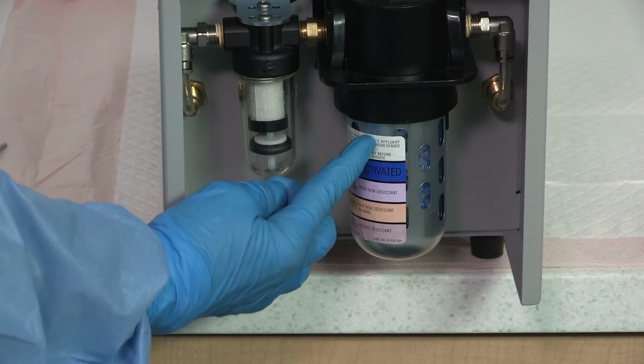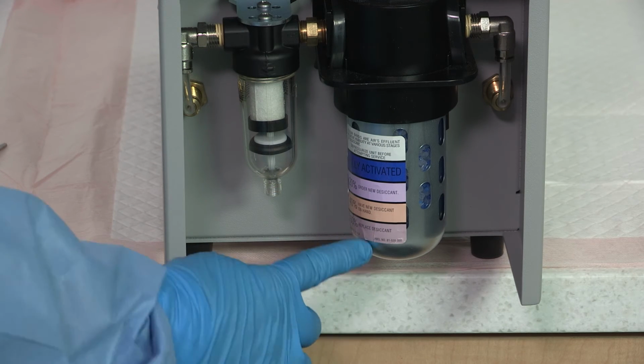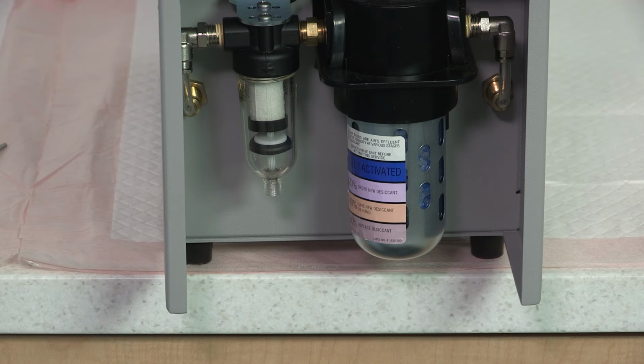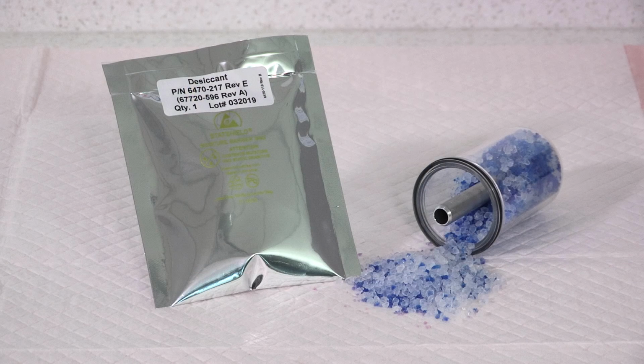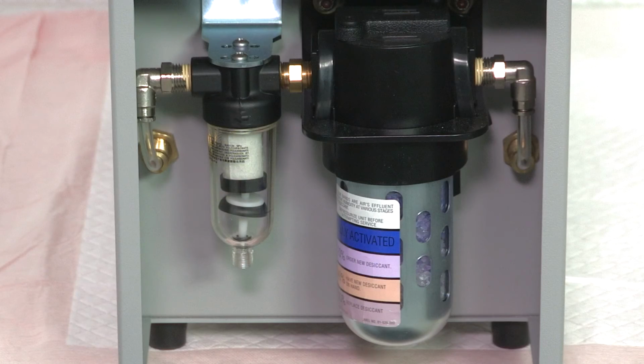Compare the crystals to the color-coded comparison chart located on the metal housing of the crystal bulb. Replace as needed. The crystals are blue and white in their active state. The color of the drying crystals changes as they absorb moisture. Once they are saturated, they turn a pale pink color to indicate they need to be replaced.